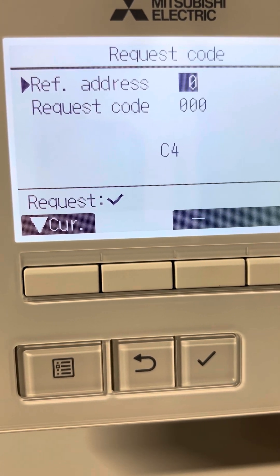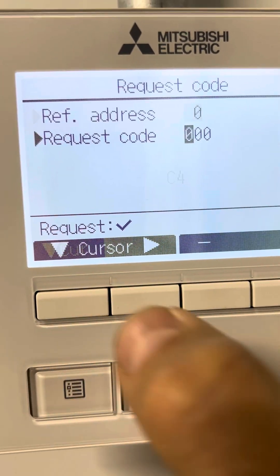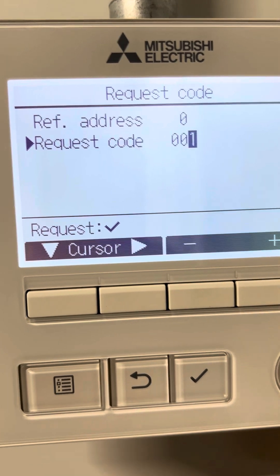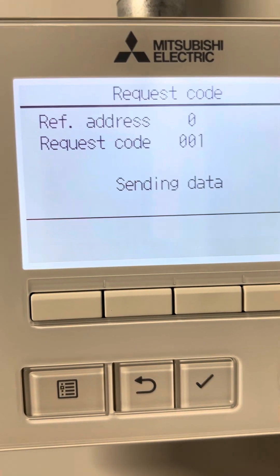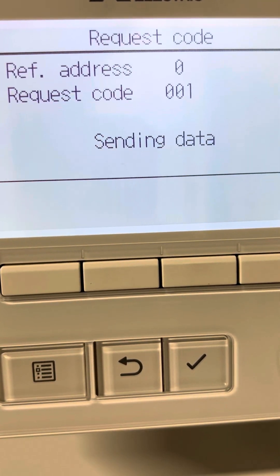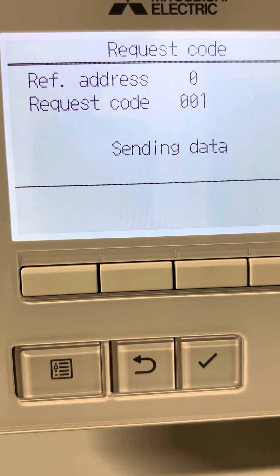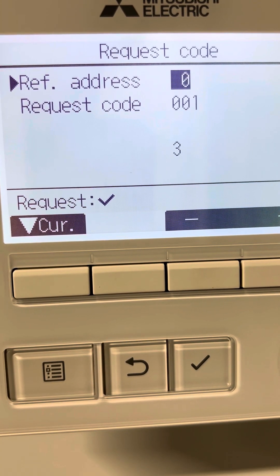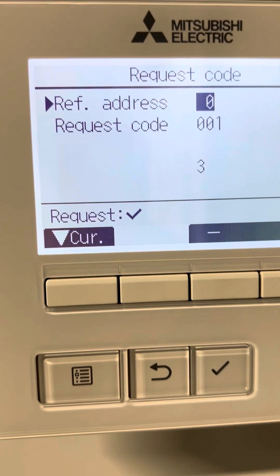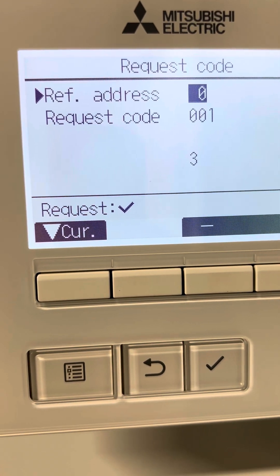If I want to get the compressor current on this unit, I go to Request Code and enter number 1. Request code 1 will give me the compressor current. At the moment the compressor current is 3 amps.